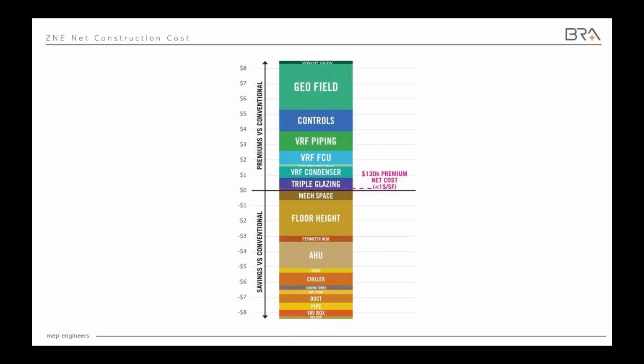Now that's all well and good that we picked the best of those 3, but those were all net zero, right? What does it cost to build net zero compared to a conventional business as usual high performance design? Well, we did spend almost $9 million premium on the geothermal bore field and advanced controls and the VRF systems and triple glazing for the envelope. So absolutely, there was a whole bunch of premiums we spent money on. But we also saved almost $9 million on reduced floor-to-floor height, reduced mechanical space, eliminating perimeter heat, smaller air handlers, getting rid of the conventional chiller plant, on and on. There was all these savings.